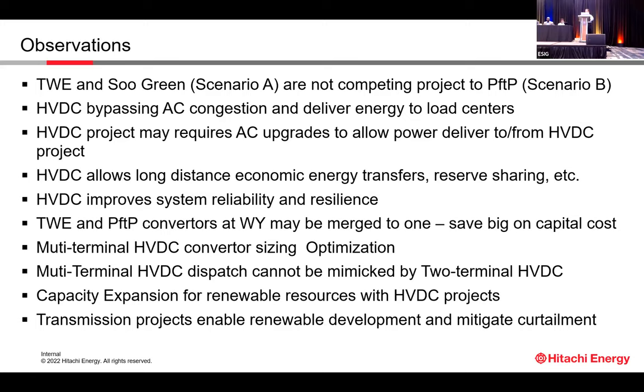For the multi-terminal HVDC converter sizing right now, we don't do the optimization. We just use 4,000 for every station. But in the phase two study, we will look at each station, how much it needs, and the sizing of the converter will be optimized. Also, the control optimization of a multi-terminal HVDC cannot be mimicked by a two-terminal HVDC, especially for this size of problem.